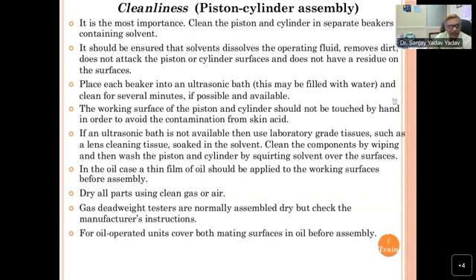Cleanliness. How to clean the piston and cylinder? It should be ensured that the solvent dissolves the operating fluid, removes dirt, does not attack the piston cylinder surface, and does not leave a residue on the surfaces. Place each in a beaker in an ultrasonic bath if you have the facility, and clean for several minutes if possible. The working surface of the piston should not be touched by hand. Otherwise, skin impressions or grease from the hands may contaminate it. If an ultrasonic bath is not available, laboratory grade tissue papers such as lens tissue paper are very essential. Soaked in this solvent, you can clean the piston and cylinder. In the oil case, a thin film should always be applied when you are keeping the piston and cylinder. Dry all parts using clean gas or air. And then for oil operated units, wet both surfaces in oil.